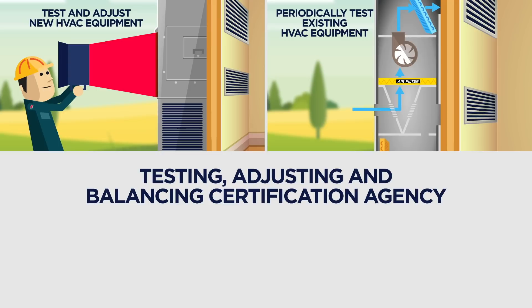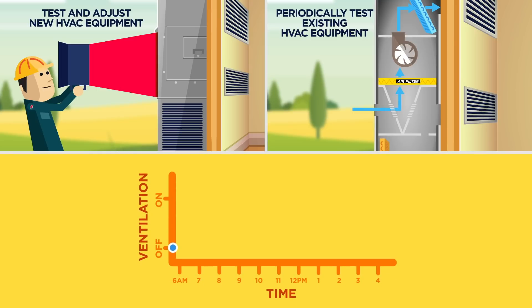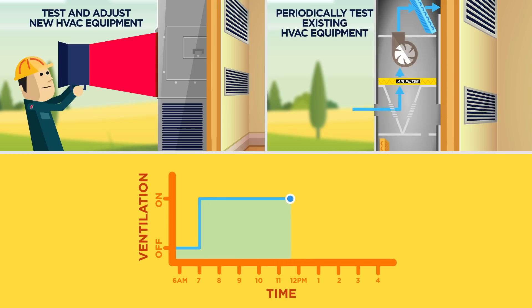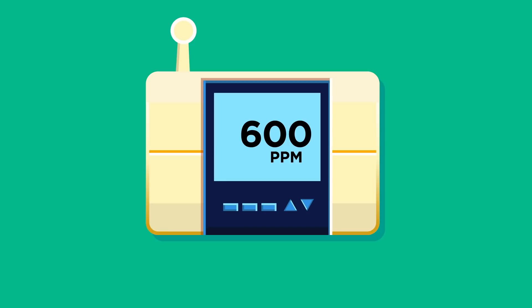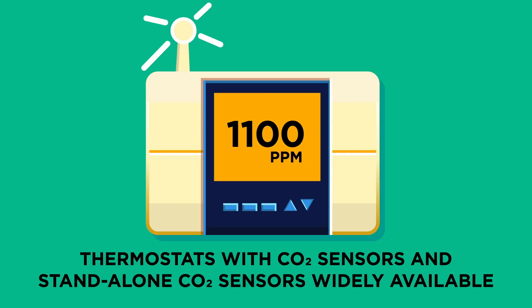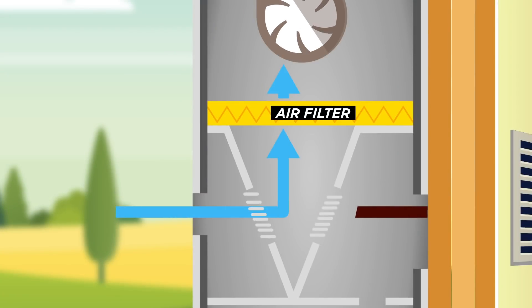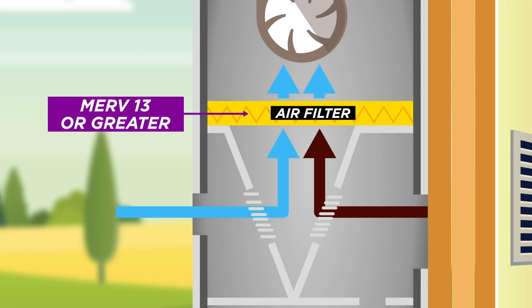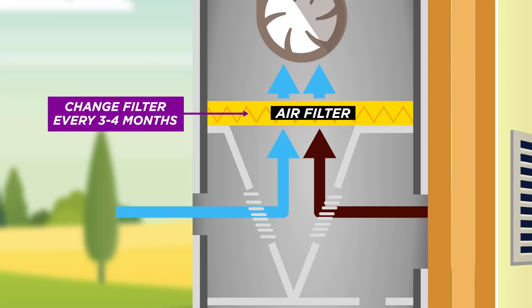Hire contractors and technicians that are certified by a testing, adjusting, and balancing certification agency. Ensure that building control systems and thermostats are programmed to operate ventilation fans one hour before school starts and continuously during the school day. Inform teachers on the importance of operating ventilation fans continuously. Install sensors in classrooms to continuously monitor CO2 levels and detect potential ventilation problems. Thermostats with integrated CO2 sensors and standalone sensors are widely available. When possible, use filters with a minimum efficiency rating value, or MERV, of 13 or greater to remove small particles from the air. Change filters every three to four months during the school year so that airflow is sufficiently maintained.